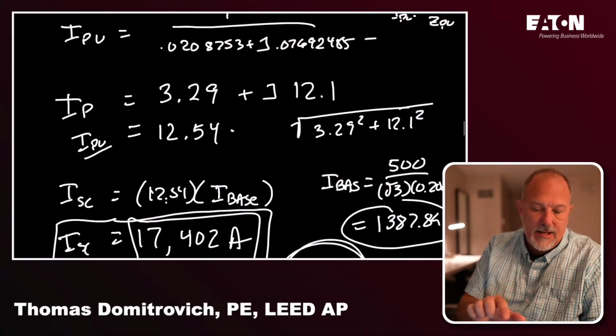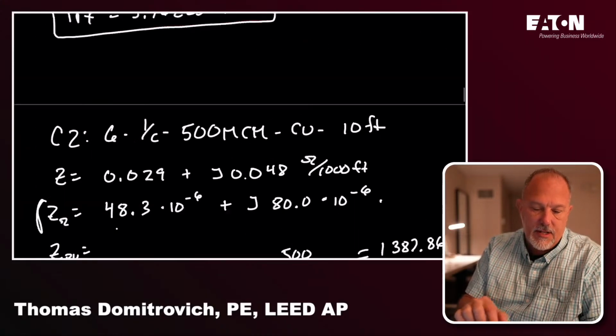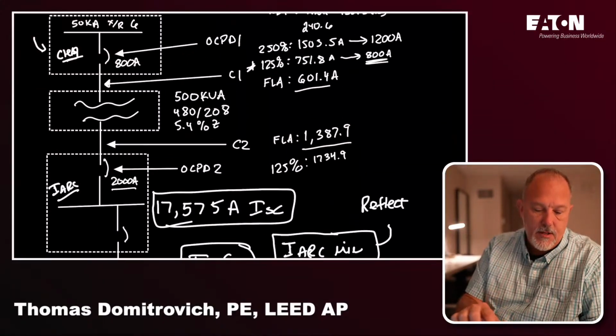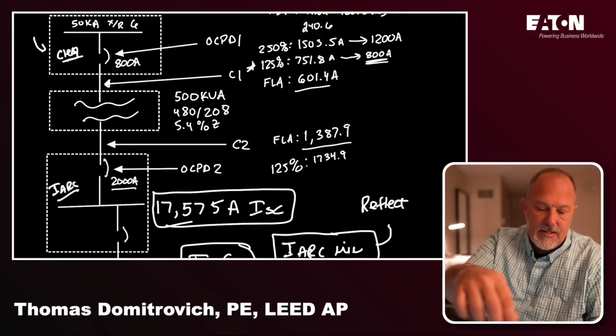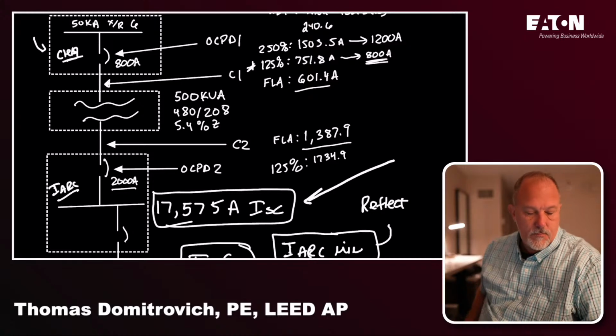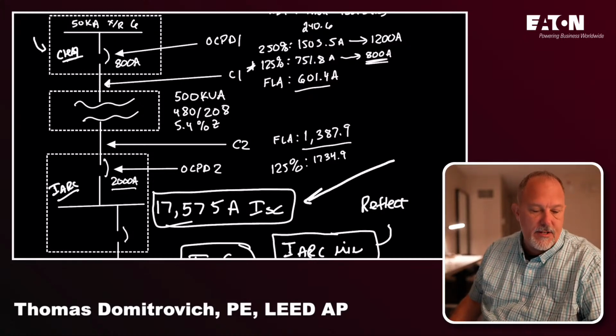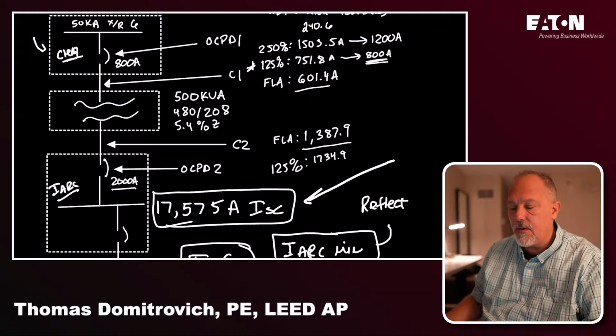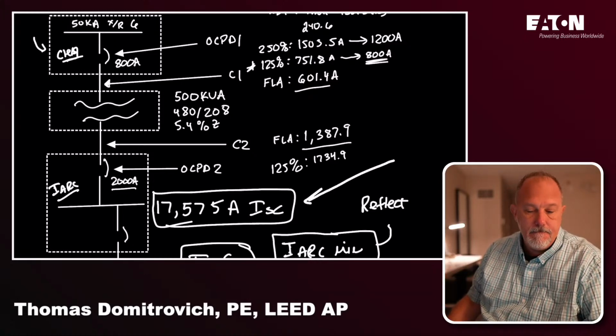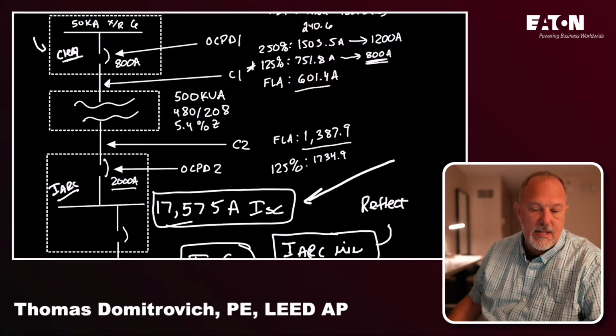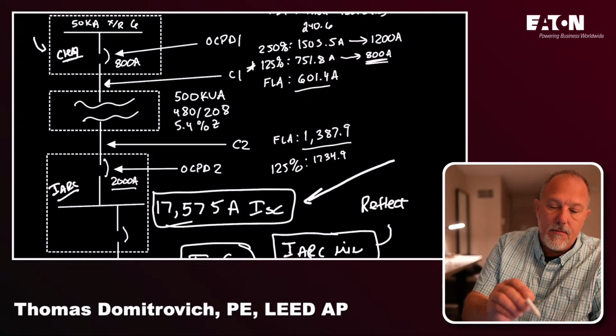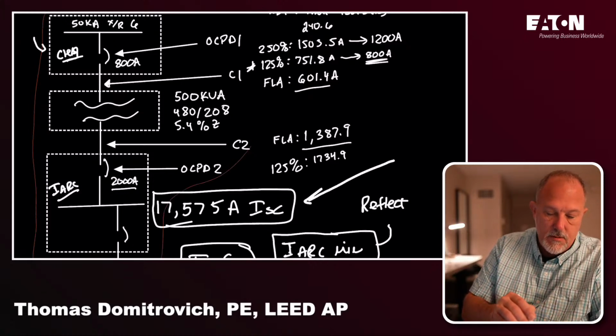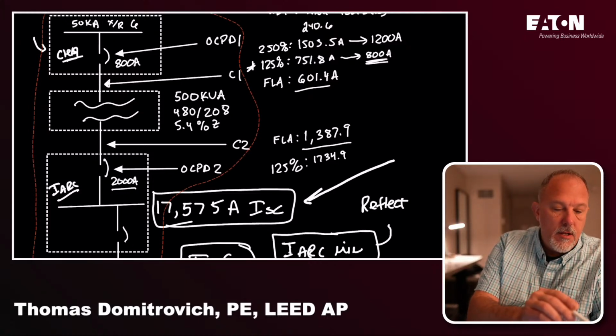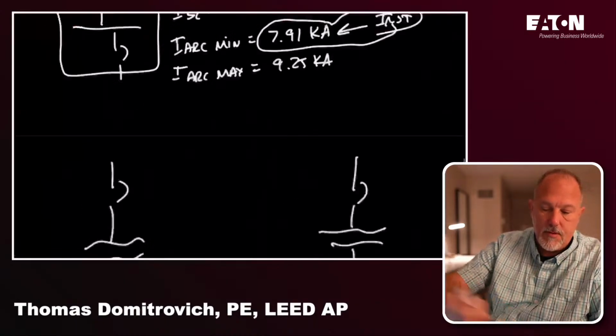So what we just did, Alan, was we verified our calculation. What is it? Let me scroll up. We did this. We verified that number. We modeled the 500 kVA transformer, 800 amp. We selected an overcurrent device on the primary. We selected the secondary overcurrent device, and what we did in the second scenario was this. Copy this. Hit copy. All the way down to the bottom and hit paste.